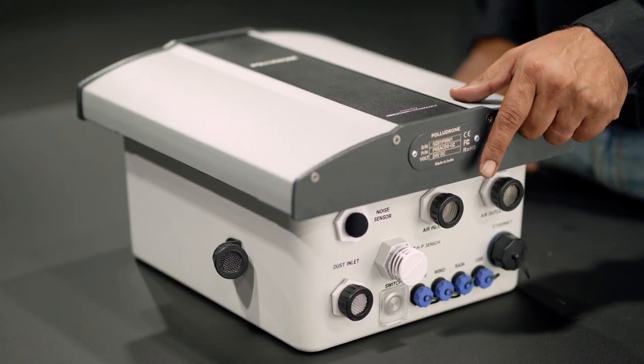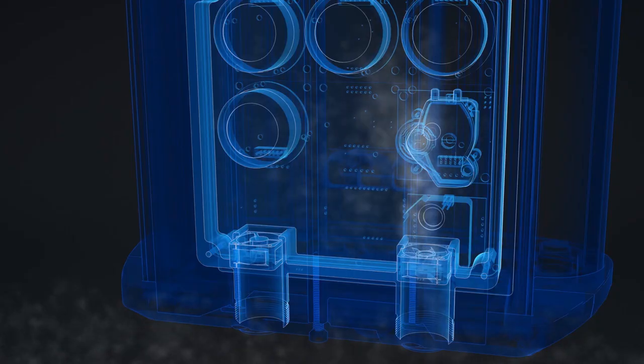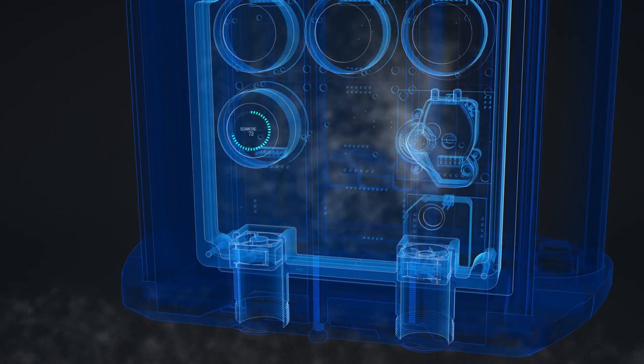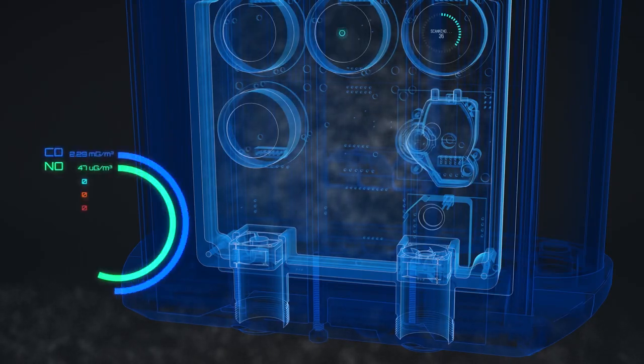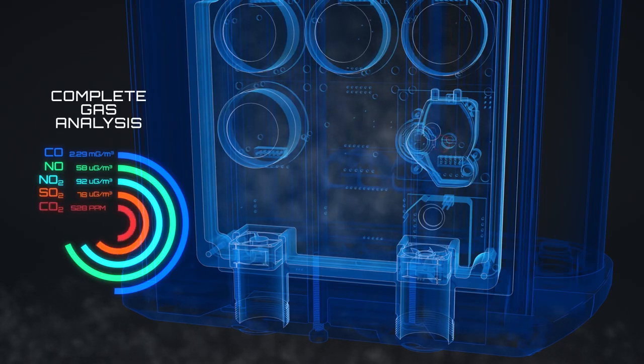Apart from dust, gases like SOx and NOx are also major causes of respiratory diseases. The Polludrone measures toxic gases through active sampling by taking a sample of air through this inlet every 2 minutes. This sample is analyzed by different gas sensors working on proven principles like electrochemical, NDIR and PID. Complete gas analysis is done by measuring the concentration of SOx, NOx, ozone and carbon oxides.